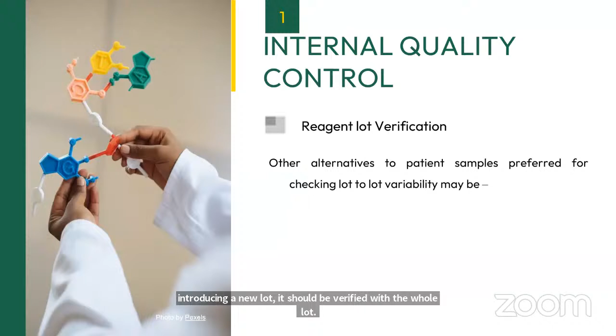Other alternatives to patient samples for checking lot to lot variability may be reference materials or QC products. So the first choice should be patient samples. You should check the patient sample with the previous lot and with the new lot as a part of reagent lot verification. If patient samples are not available, then the other options are using a reference material or QC product.